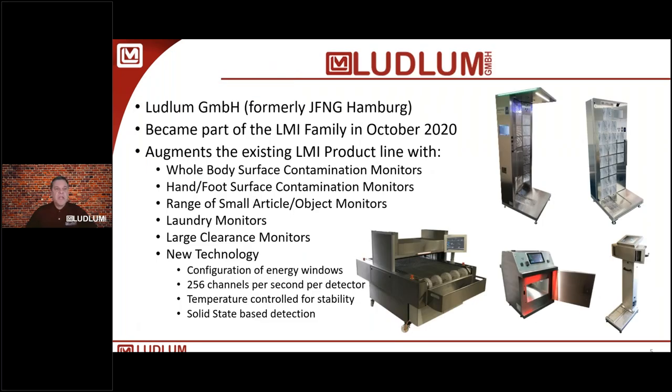Ludlum GmbH, formerly James Fisher Nuclear Group in Hamburg, became part of the LMI family in October 2020. They augment our existing product line with whole body surface and contamination monitors, foot monitors, small object monitors, laundry monitors, and very large clearance monitors. They brought a new technology that allows configuration of energy windows — 256 channels per detector — with temperature-controlled detectors for stability. This is primarily a SiPM technology combined with plastic scintillators.